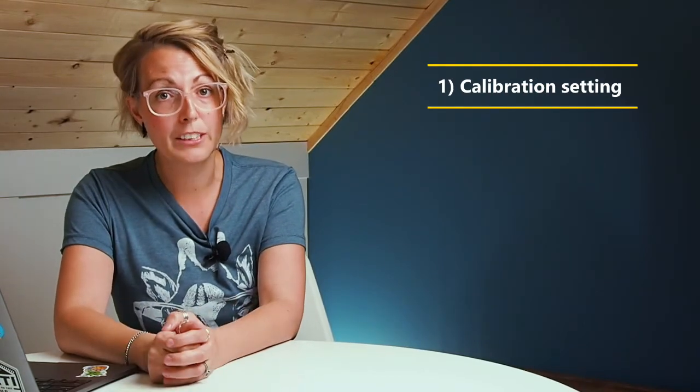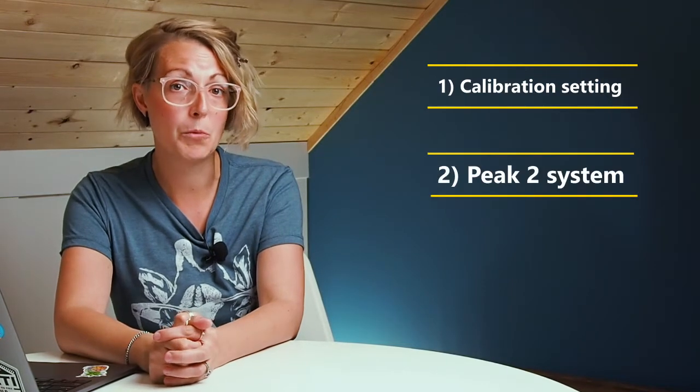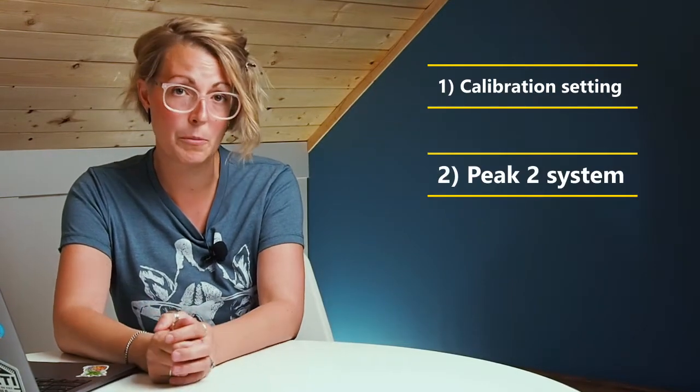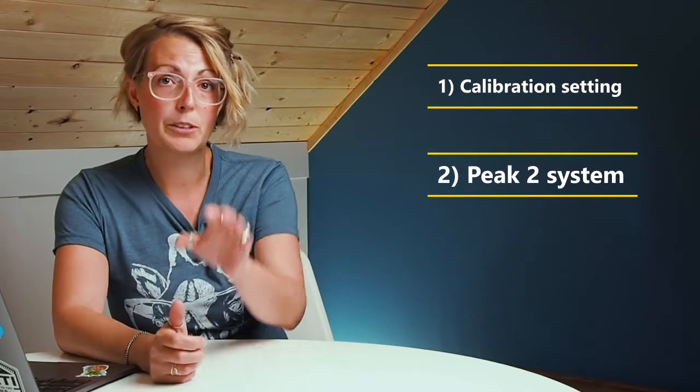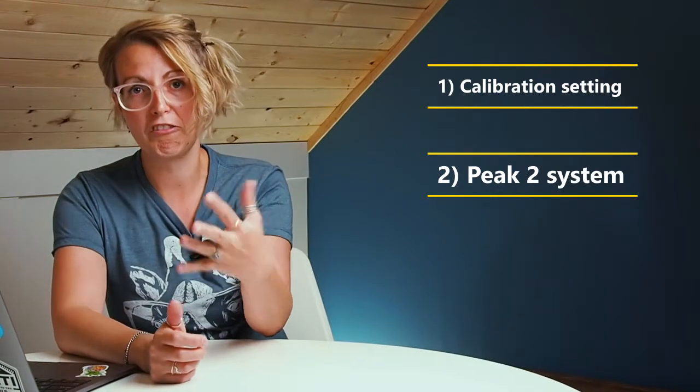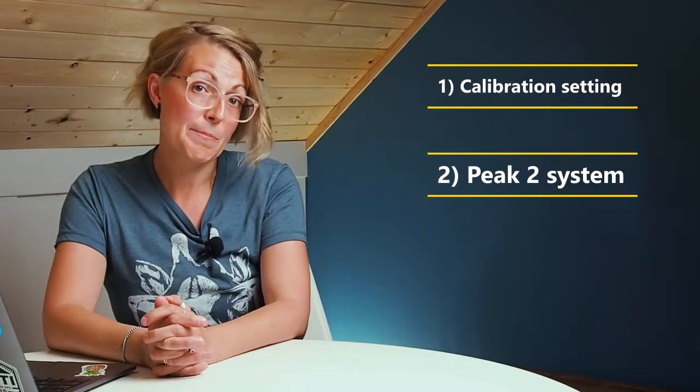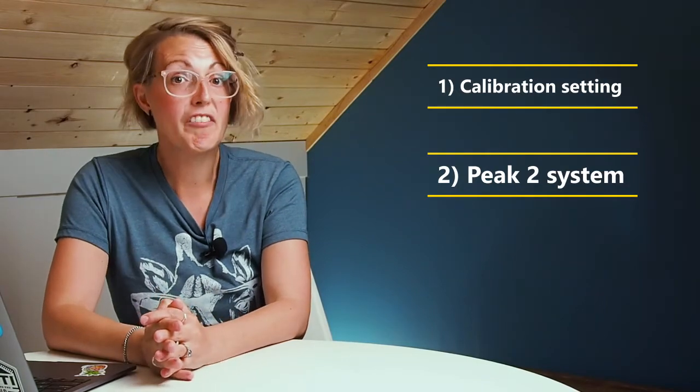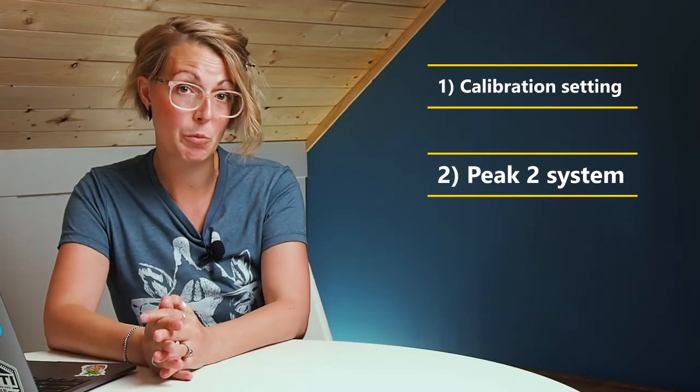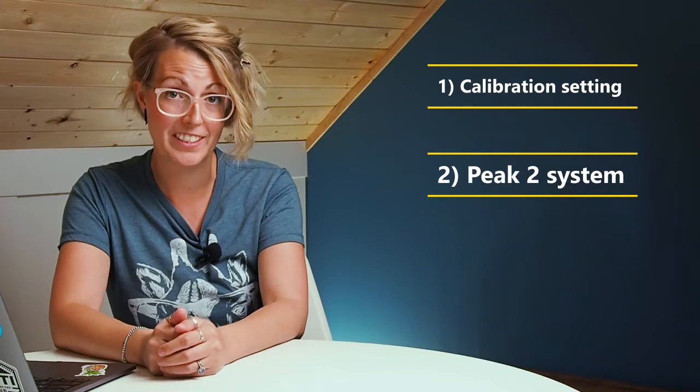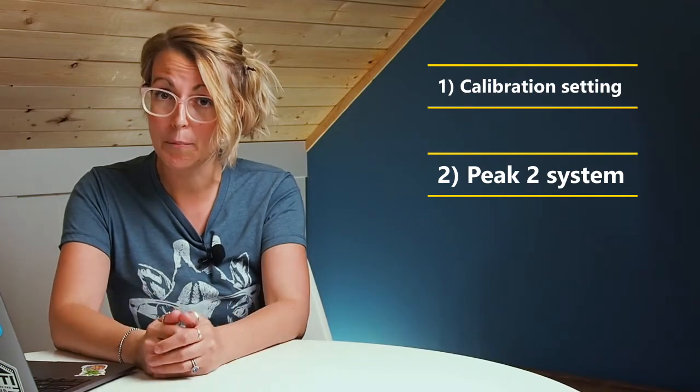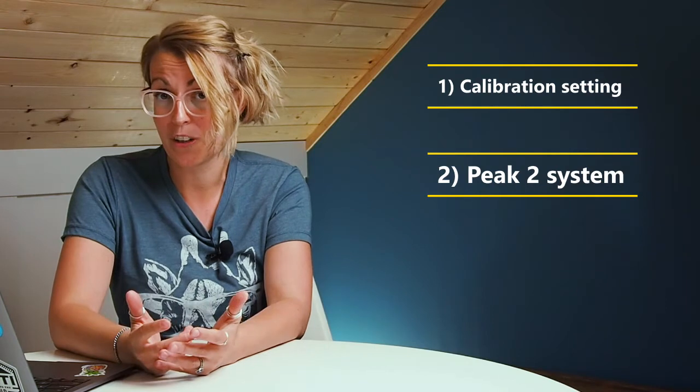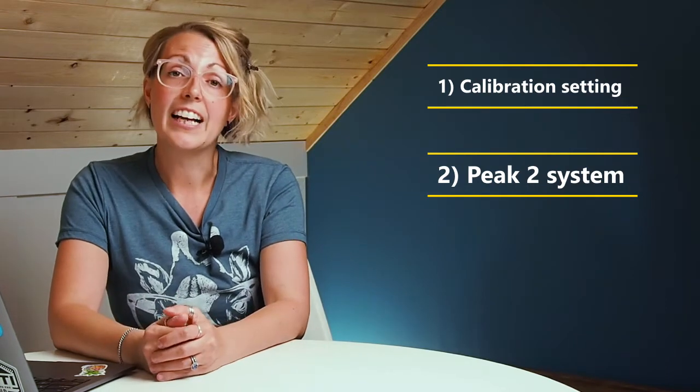The other method we talked about is the peak 2 system, where you use rainbow beads or another form of beads with multiple peaks and look for the point where the signal inflects. Both these methods can work very nicely. However, both rely on using beads which may have an inherently different fluorescent signature than your cells and may not be the optimal PMT voltage for your experimental setup.